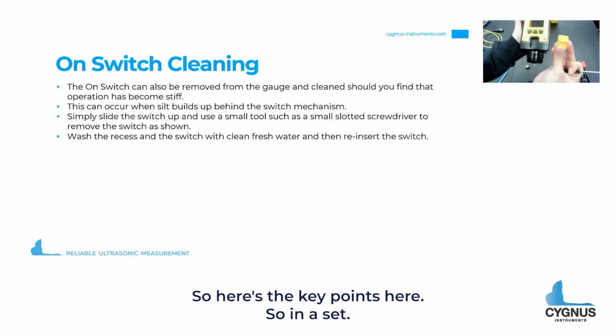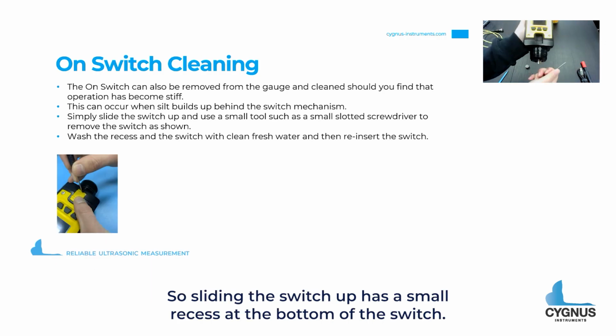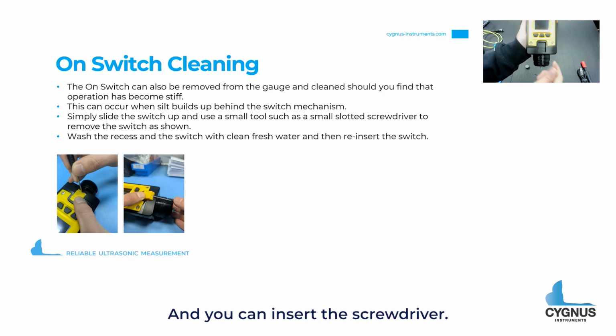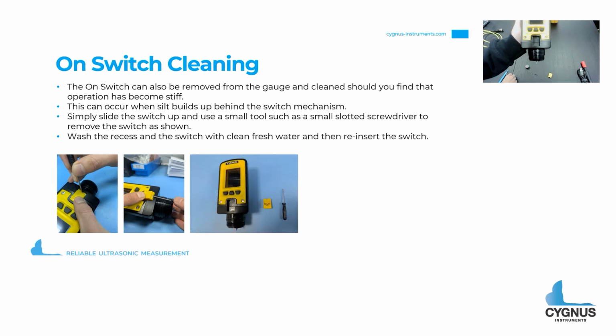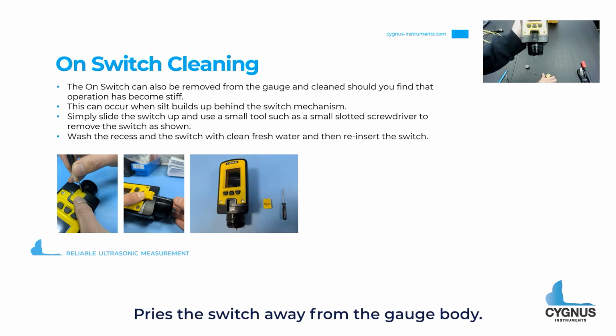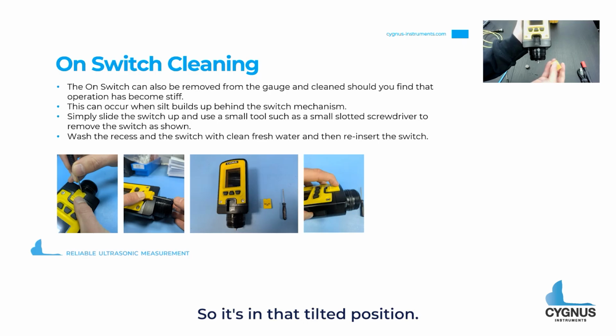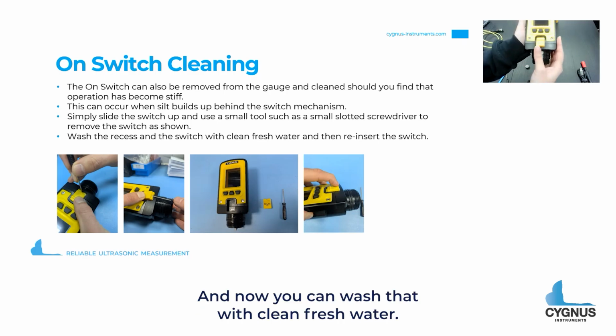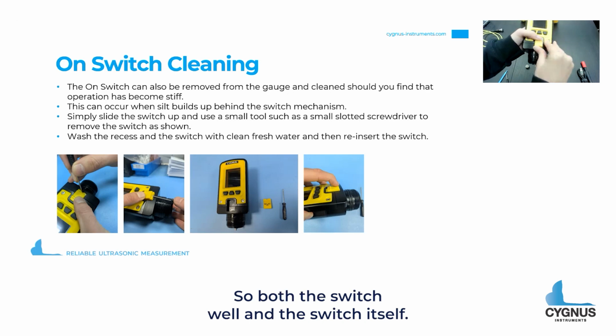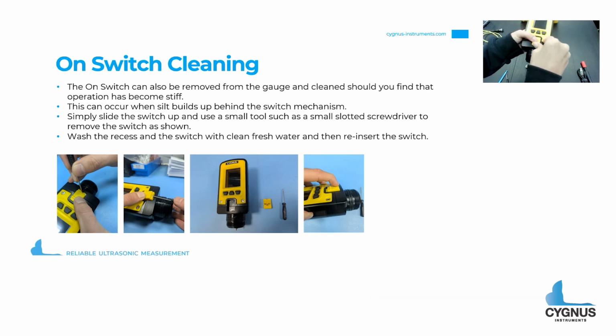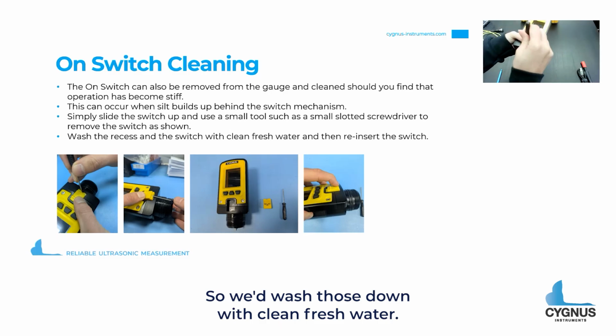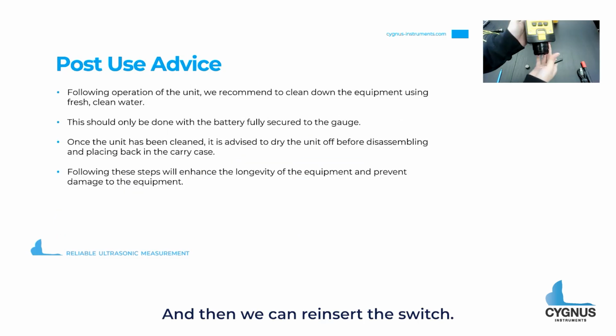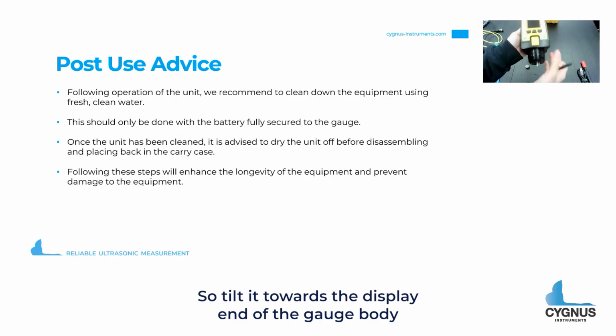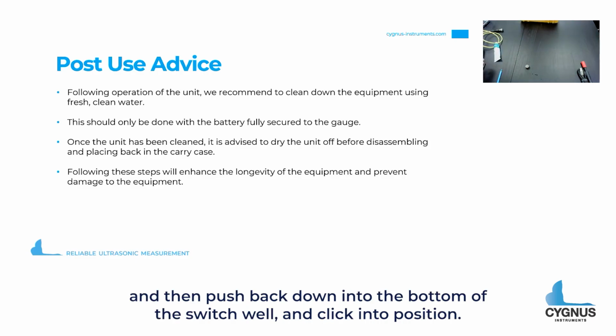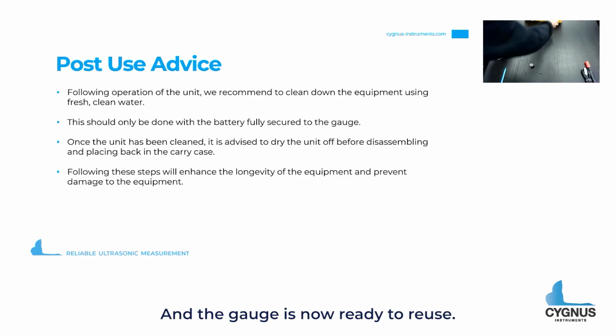So here are the key points. Slide the switch up, there's a small recess at the bottom of the switch and you can insert the screwdriver. Prise the switch away from the gauge body, so it's in that tilted position. Remove the switch, and now you can wash both the switch well and the switch itself with clean fresh water, and then we can reinsert the switch. Tilt it towards the display end of the gauge body, and then push back down into the bottom of the switch well, and click into position. And the gauge is now ready to reuse.